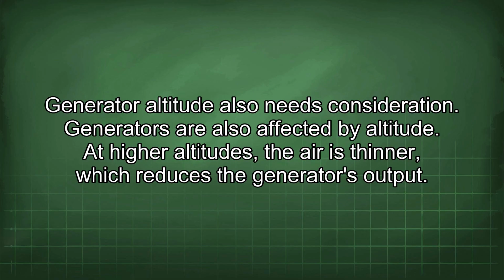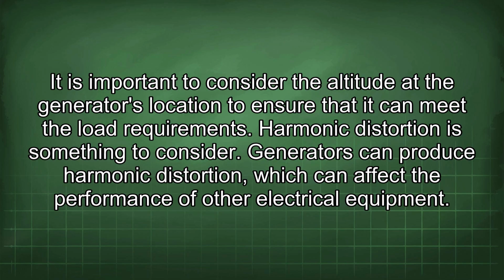Generator altitude also needs consideration. Generators are also affected by altitude. At higher altitudes, the air is thinner, which reduces the generator's output. It is important to consider the altitude at the generator's location to ensure that it can meet the load requirements.